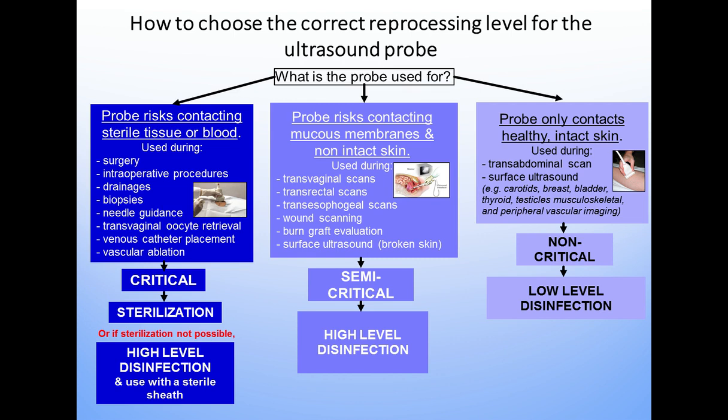If the probe were to contact mucous membranes or non-intact skin, so that would be all endocavitary procedures, procedures where there was a rash, scanning partially healed wounds and so on, that device would be considered semi-critical and should be minimally high-level disinfected.